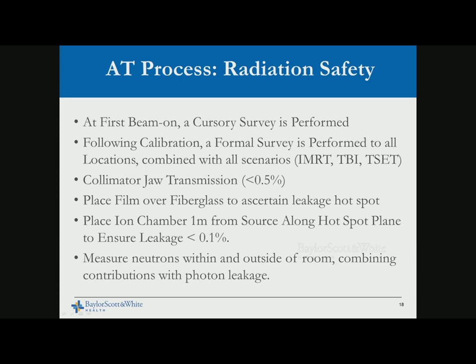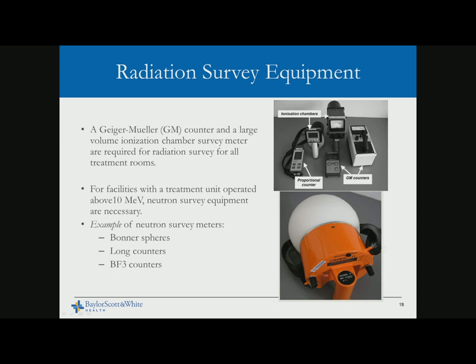Equipment needed for radiation survey includes a Geiger-Müller counter and a large volume ion chamber. The GM counter helps identify cracks in shielding or unintended holes. The large volume ion chamber allows you to determine instantaneous dose rate — whether your occupational or public limits are met depending on whether the area is controlled or uncontrolled. For energies greater than 10 MeV, neutron detection using boron trifluoride counters or bubble counters should be used to quantify neutron contribution.